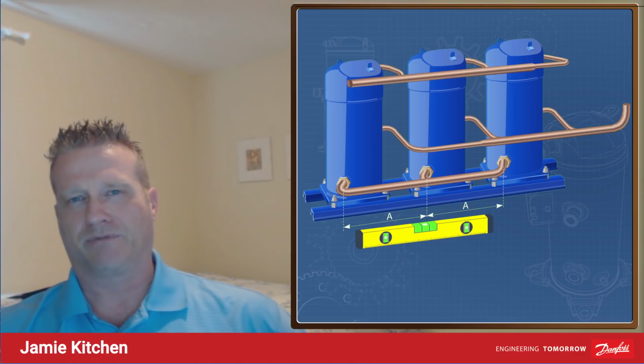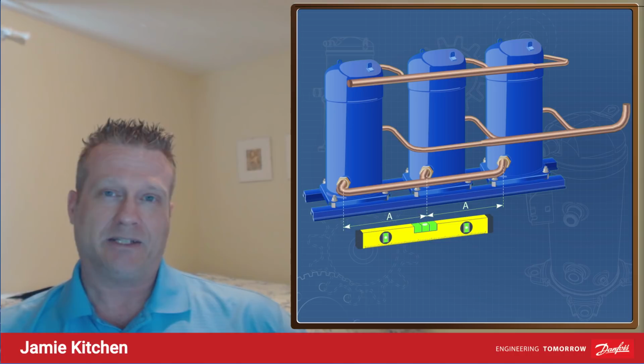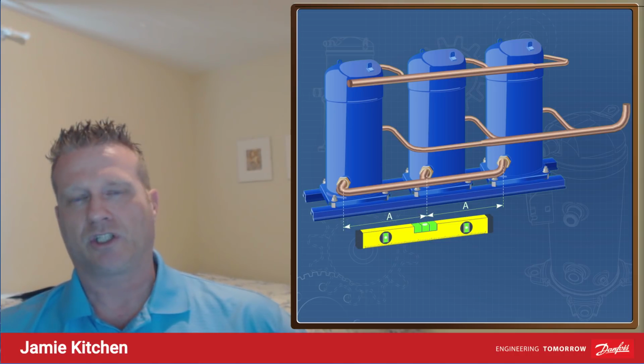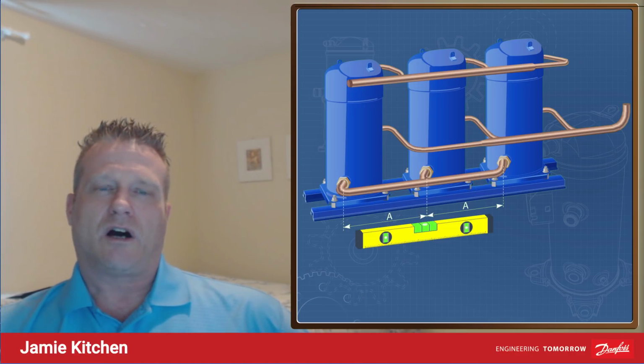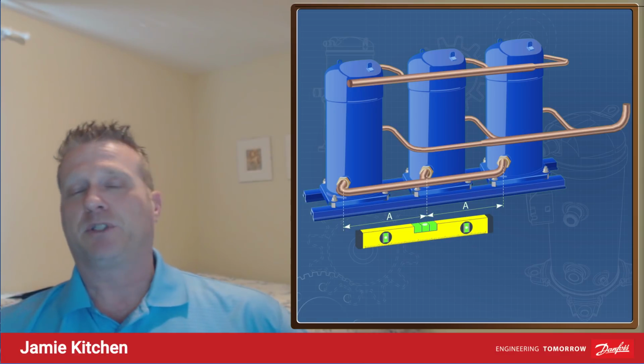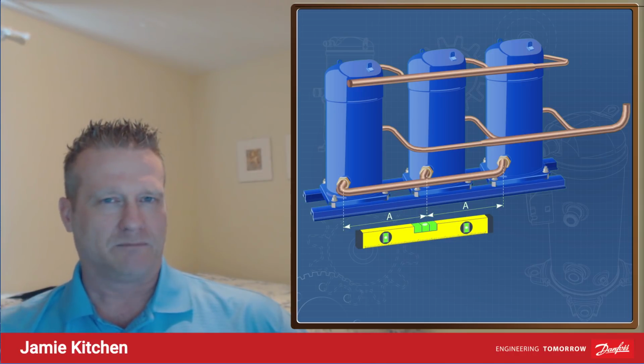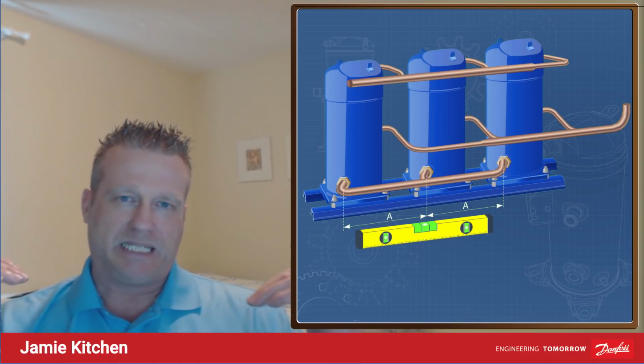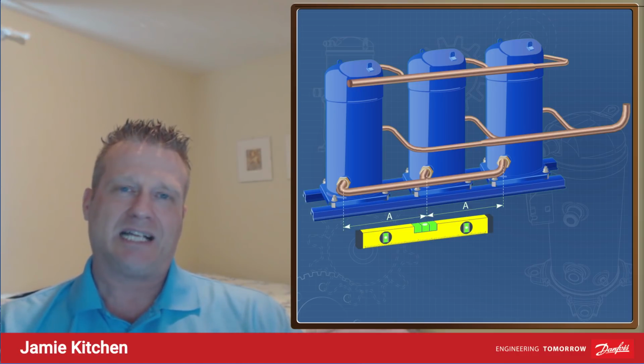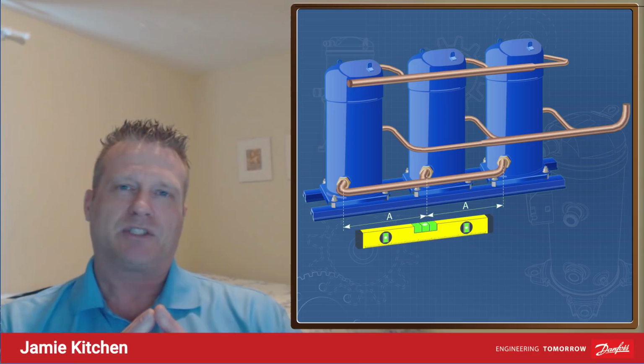Now, oil and tar roofs don't mix very well together, and you can end up in lawsuits and all kinds of other issues. What ended up happening was this was a tandem application, 2 compressors operating in tandem, which means they share the same suction and discharge headers or connections. They're not allowed to move independently of each other. Okay, they have to be fastened securely to a common rail. They should not vibrate or be able to move independently of each other. There may even be a securing bracket that goes across their heads that attaches them to each other. They cannot move independently because they share a common suction and discharge.